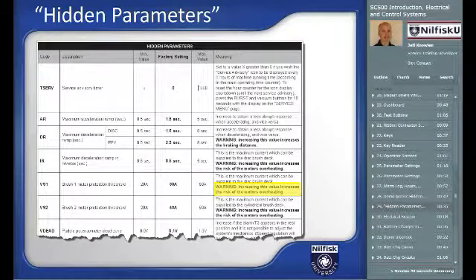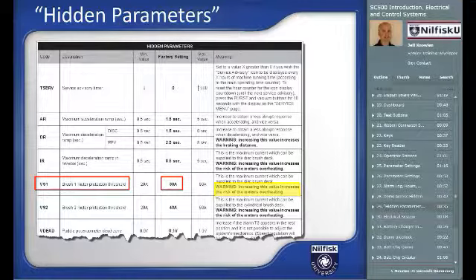For example, look at the VS1 Brush 1 motor protection threshold. The factory setting uses 30 amps as an alarm code threshold. If the controller sees more than 30 amps for a certain period of time, it will shut off the scrub motor and set an alarm code. This is to protect the motor from overheating. If you increase this value, the motor could overheat during operation.